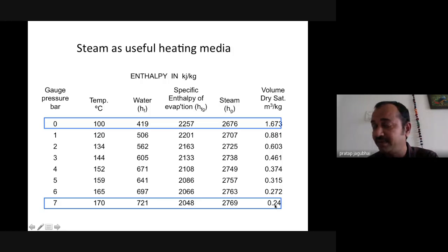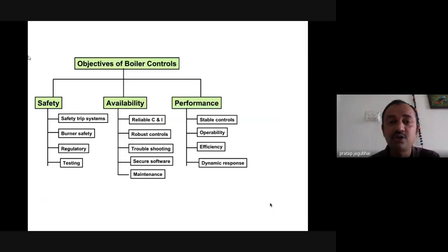So the higher temperature, high pressure steam becomes more dense, like a revolver bullet, and it is very difficult to control. For that we need proper safety and statutory regulations for handling the steam and combustion equipment. And that is the reason we need boiler instrumentation and control.